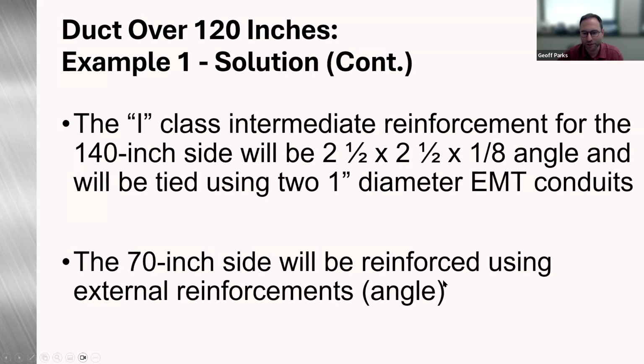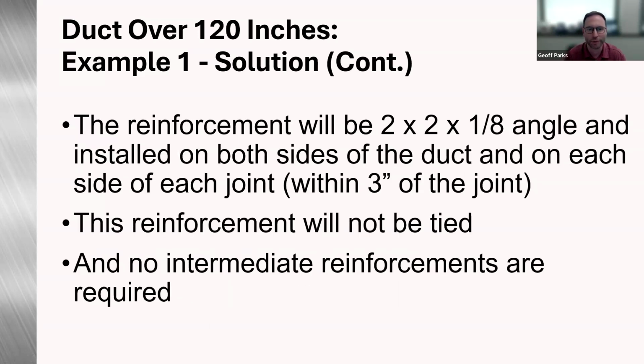And then looking at the 70-inch side, since this is under 120, we would have gone to these, what I'm calling standard duct construction tables. And the solution would have been 2 reinforcements on either side of the joint. And those would have been 2 by 2 by 1/8 inch angle. And again, those would be installed on both sides of the joint and on each side of the joint within 3 inches.